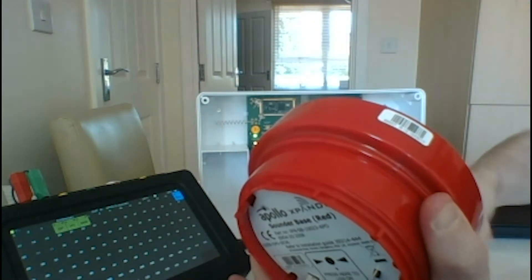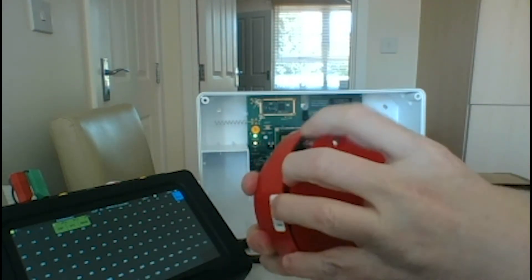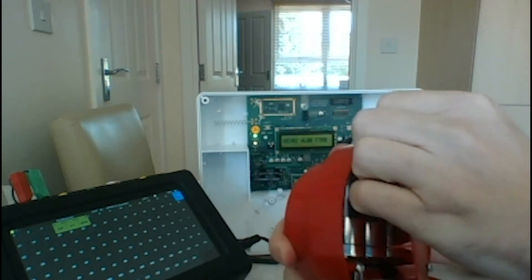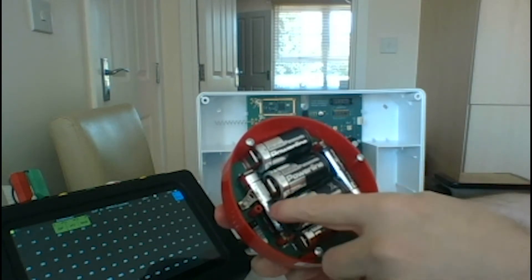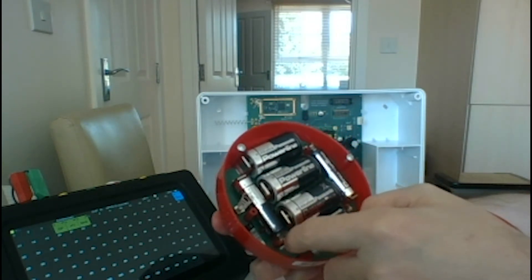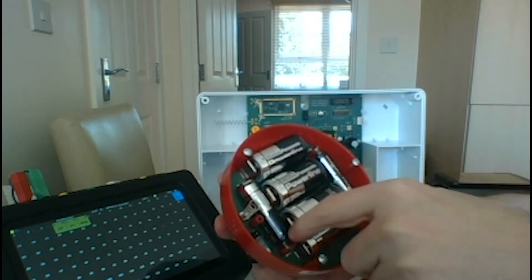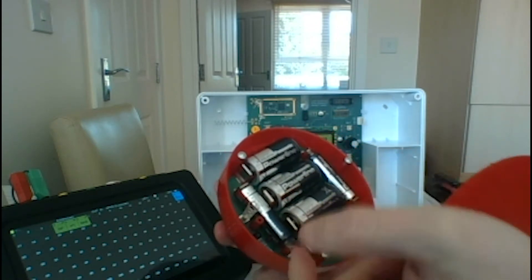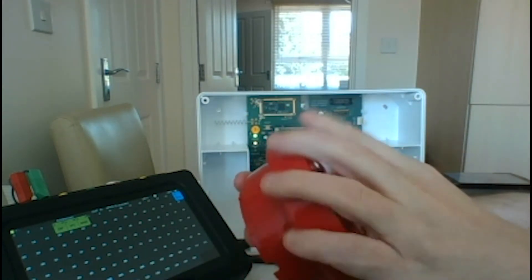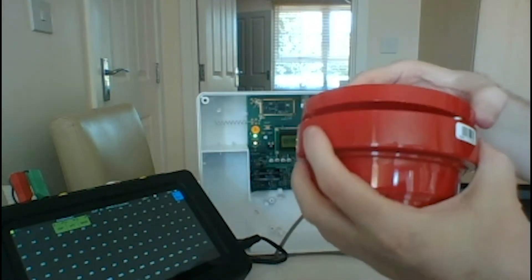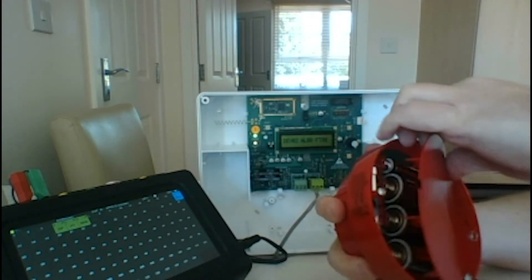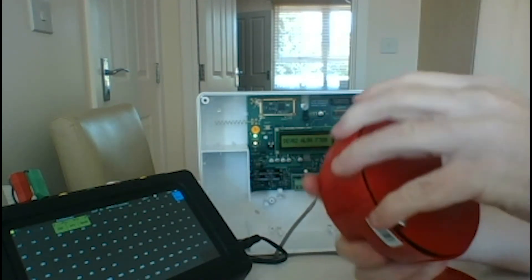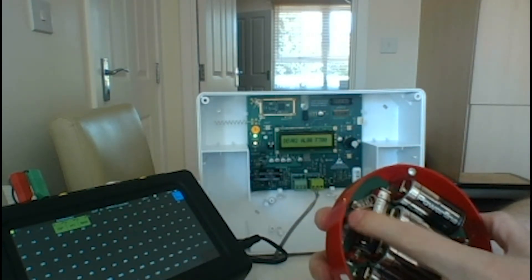In the back, you've got a base battery cover which you can remove. Under there, you've got three C-size alkalines and three AA-size alkalines. It's alternating between the two, and it will use these if it's actually sounding. Whilst we're in the back of the sounder, you've got the battery jumper there and the tamper spring as well. So it's all powered and ready to go.